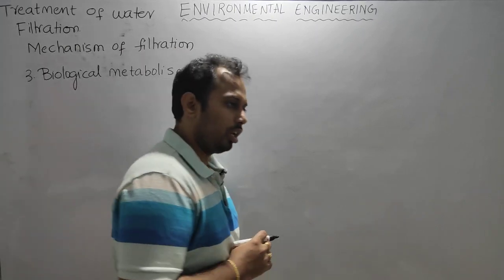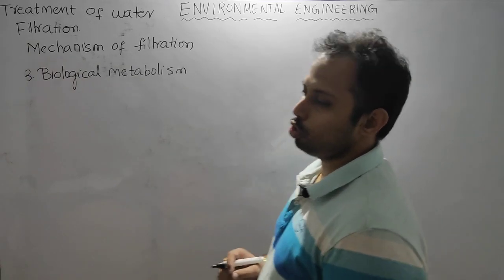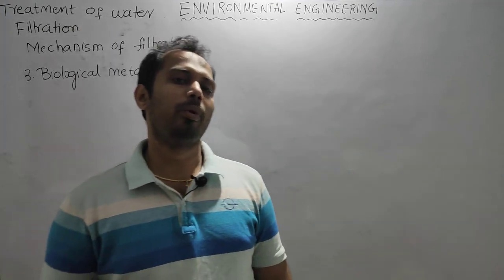Unless this dirty skin is formed, we don't consider the filtered water fit for drinking. Up to the formation of the Schmutzdecke, we leave the filtered water unused and don't consider it as filtered water. Once the formation is over, we take the water coming out of the filter as filtered water. That much is the importance of the Schmutzdecke. The filter media is not fit for filtering unless it is formed.